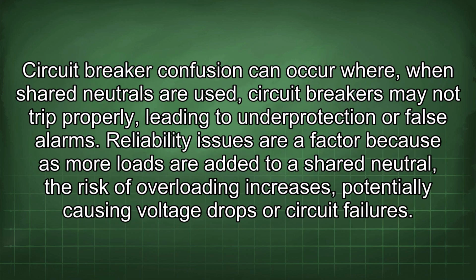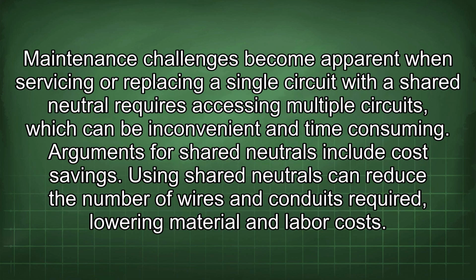Circuit breaker confusion can occur where, when shared neutrals are used, circuit breakers may not trip properly, leading to underprotection or false alarms. Reliability issues are a factor because as more loads are added to a shared neutral, the risk of overloading increases, potentially causing voltage drops or circuit failures. Maintenance challenges become apparent when servicing or replacing a single circuit with a shared neutral requires accessing multiple circuits, which can be inconvenient and time-consuming.